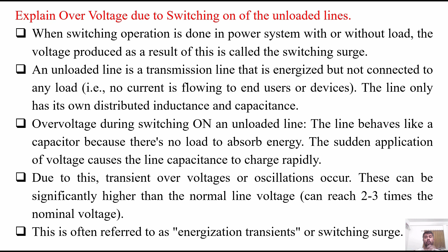Overvoltage during switching on an unloaded line. When this is done, the line behaves like a capacitor because there is no load to absorb the energy that is given to the line. The sudden application of voltage causes the line capacitance to charge rapidly. Due to this, transient overvoltages or oscillation occurs. This can be significantly higher than the normal line voltage and can reach 2 to 3 times the nominal voltage. This is often referred to as energization transients or switching surge.